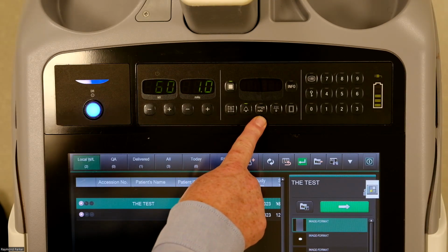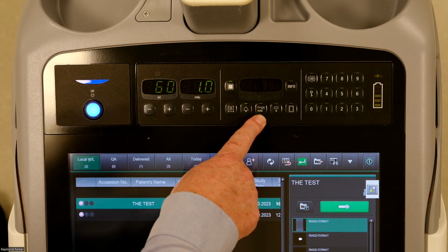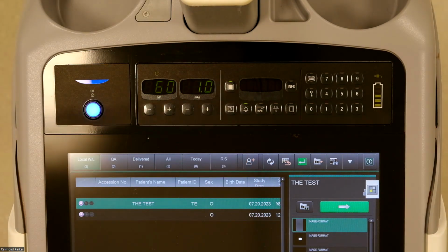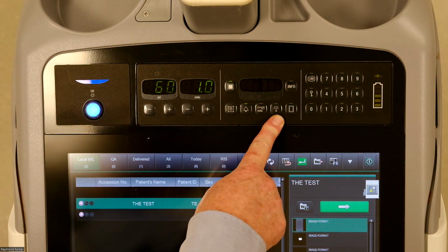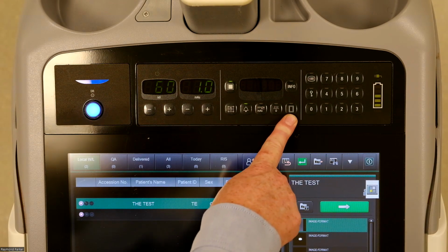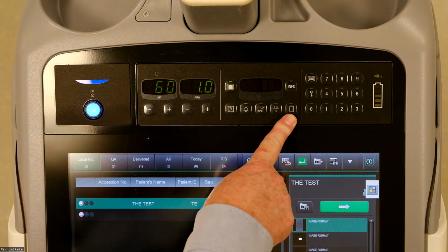This next button is your extended mAs button. The extended mAs button allows you to enter into a longer exposure time to allow you to achieve greater than 125 mAs at 80 kVp. It is only available per menu. So for each menu that is loaded, you'd have to reselect the extended mAs button here. Added filtration would be this button. Our next button is your CRDR, and I will come back to that button shortly.